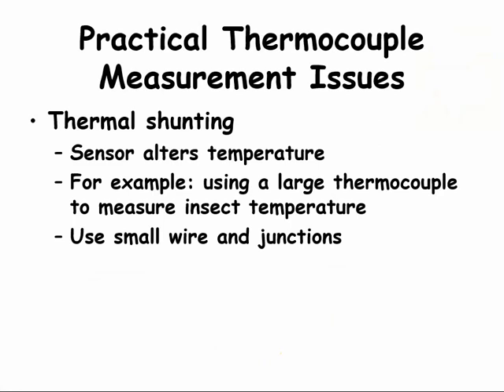Another practical thermal sensor measurement issue is thermal shunting. Thermal shunting occurs when the sensor being used is larger than the thing being measured. Thermal shunting means that the sensor is too big, so the sensor alters the thing being measured. One example might be if you were trying to measure the temperature of an insect, and you were using a large thermocouple that is larger than the insect. Are you really measuring the insect temperature? Probably not. One way to try to mitigate thermal shunting is to use extremely small thermocouple wire and small junctions.